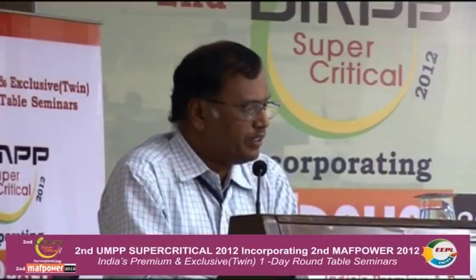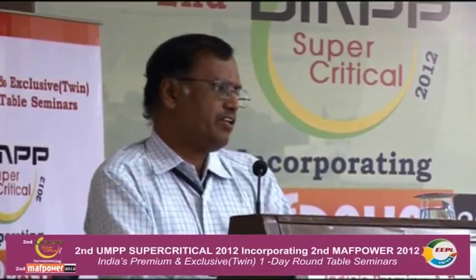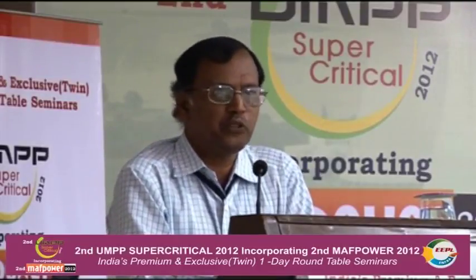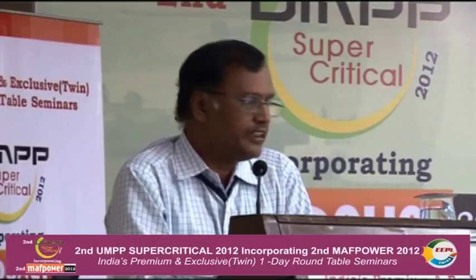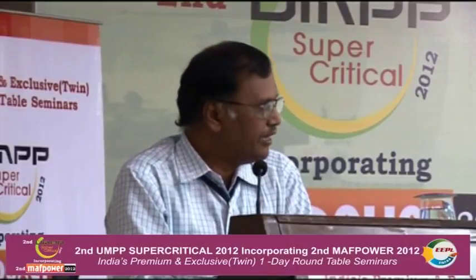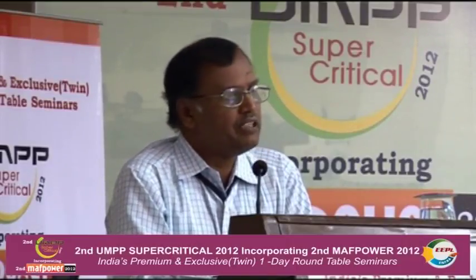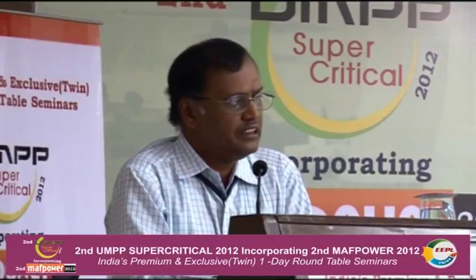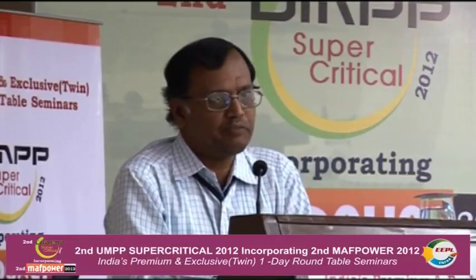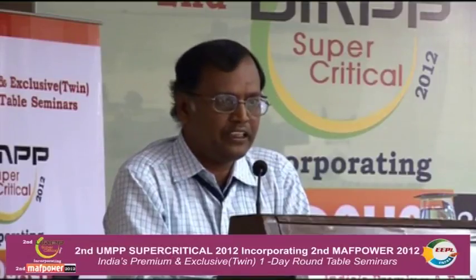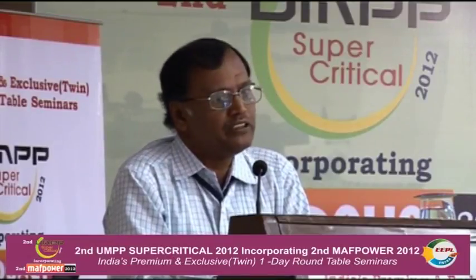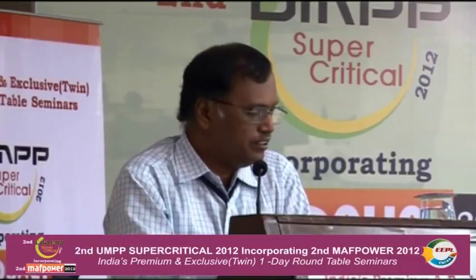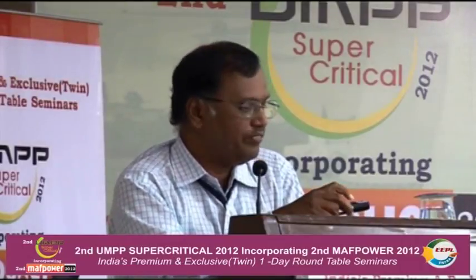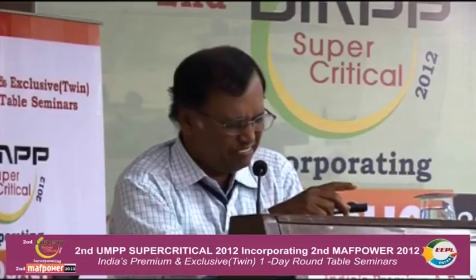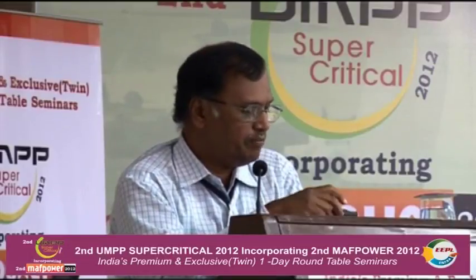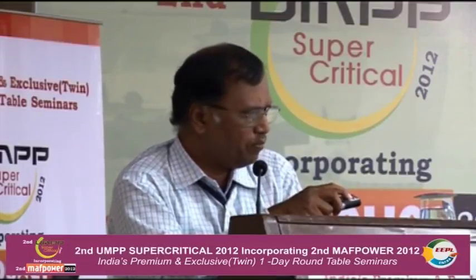This is a typical separator. For a 500 megawatt boiler, the drum is about 225 tons, a huge, thick-walled component. But here it's smaller, vertical in design. The number of separators may vary from 2 to 4 depending upon the size; generally 4 separators for a 660 megawatt unit. These 4 separators collect into a common collecting vessel, which then feeds into the circulating system for startup purposes. This is a typical header and separator manufactured at our Tiruchirappalli plant.